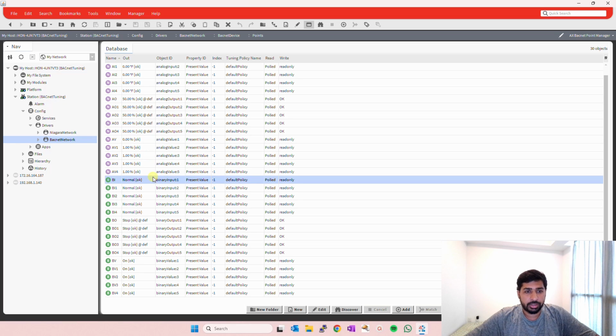Now, to mitigate this, take the temperature sensor, which is not a very fast responding variable. Any temperature variable of the equipment doesn't ramp up or ramp down by 5 degrees, 10 degrees, or even a degree in a brisk time. It takes a couple of minutes. As compared to pressure, where every second there would be a decimal change.